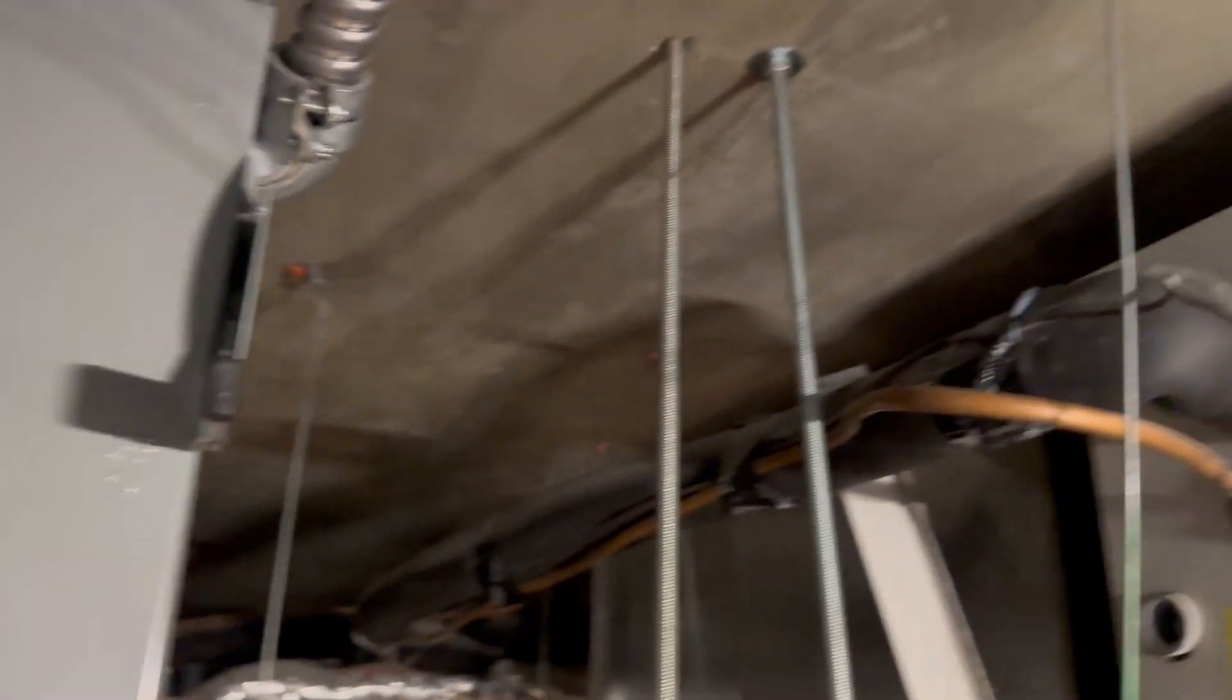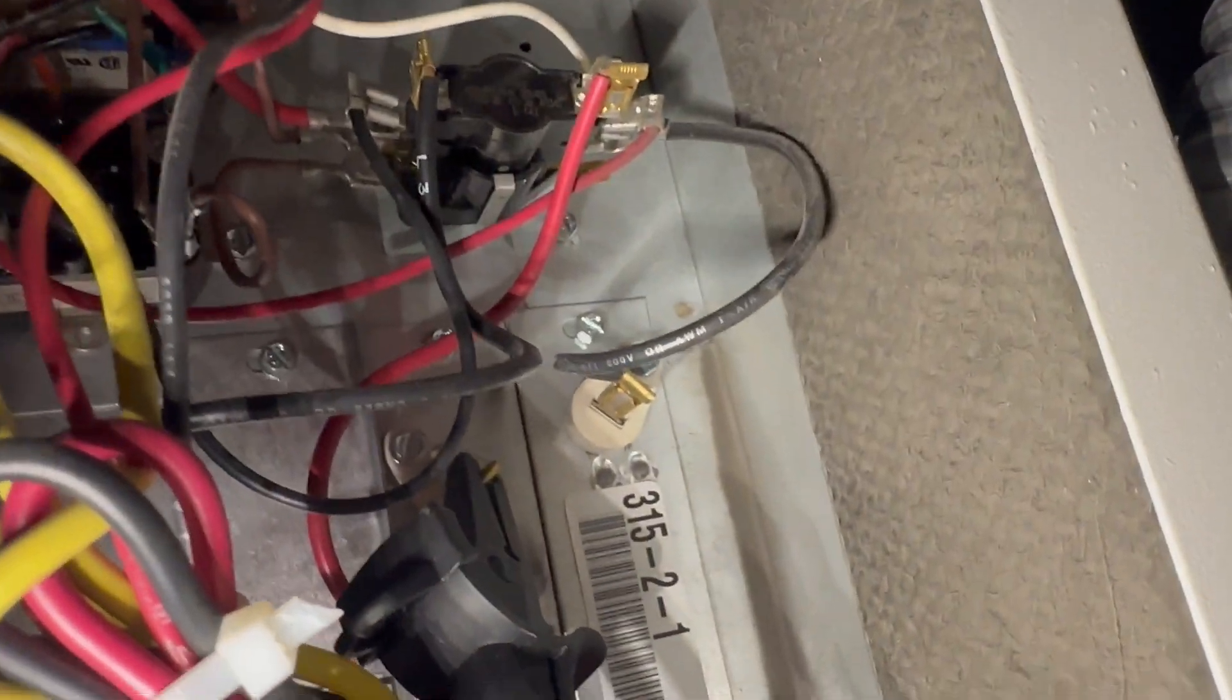Next I'm going to turn the power off and do an ohms check across each of the heating circuits. Both read 11 so I know that there's no opens in either one of these heating circuits.